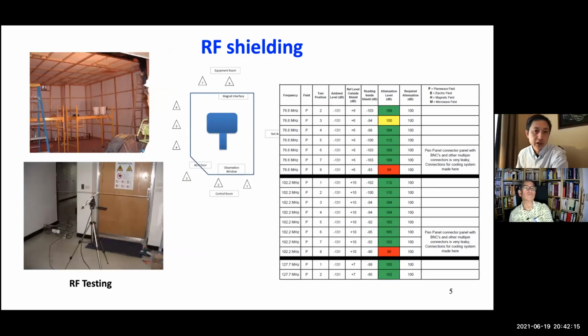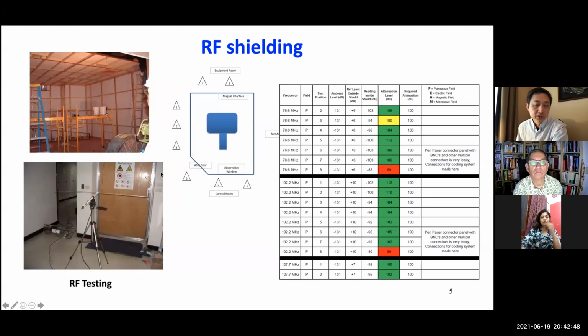So this is before MRI installation. I mentioned the RF shielding test is very important. I think most of you, if you have learned MRI, know the MRI needs to be shielded from RF. So basically that's copper around the room, and RF cannot go out and it cannot come in. So once this shielding is done, we have to test the integrity of the shielding. The testing is done by transmitting an RF at different frequencies from outside. And inside, remember the scanner is not there yet, so we use an RF antenna and check different locations.